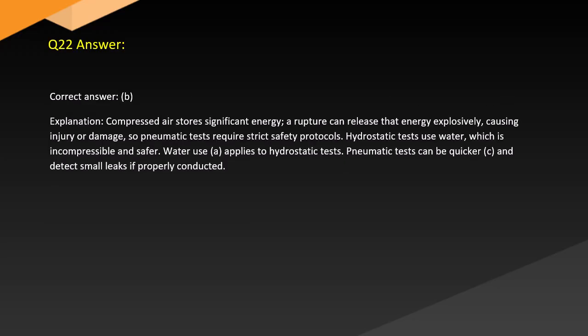Answer. Correct answer, B. Explanation. Compressed air stores significant energy. A rupture can release the energy explosively, causing injury or damage, so pneumatic tests require strict safety protocols. Hydrostatic tests use water, which is incompressible and safer. Pneumatic tests can be quicker, C, and detect small leaks if properly conducted.